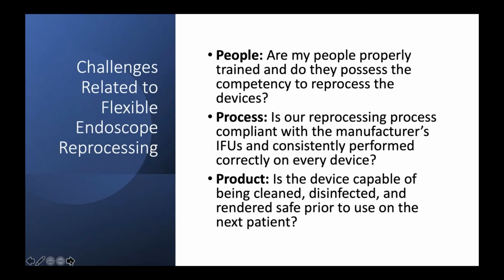And then lastly, it's really getting down to that product level, right? Whether that product is a stapler or something as sophisticated as a flexible endoscope, it doesn't matter. But is that device actually capable of being rendered safe, right? And that's really the key thing here, because a patient, when they come in, yes, the standard of care right now is not sterilization, right? For flexible endoscopes, it's really high-level disinfection. But the patient really has an expectation that that device has no bad microorganisms present in it. And so there is a disconnect between what the actual expectation of our customers are, what our patients, right?